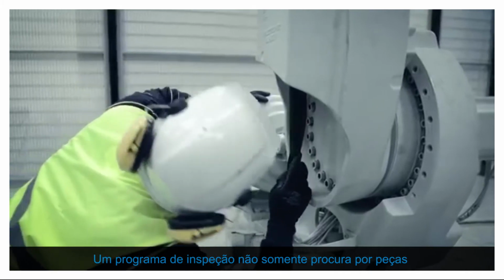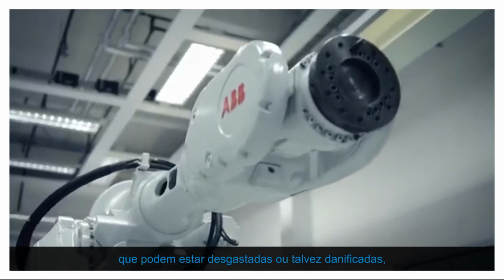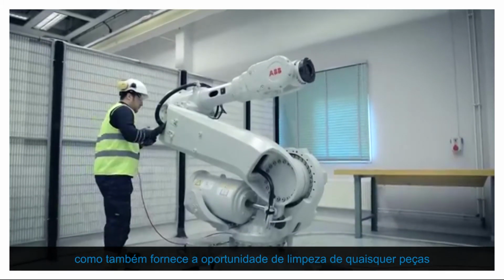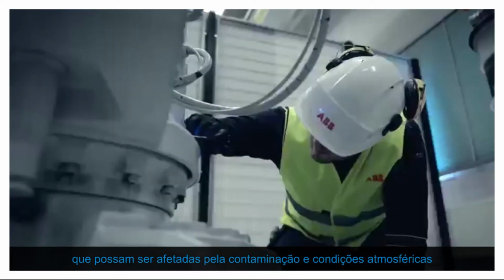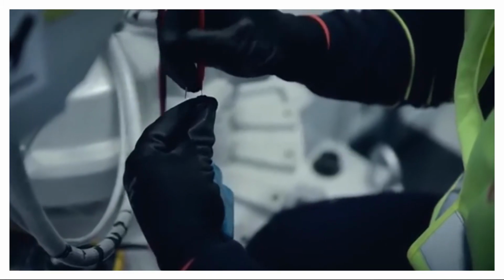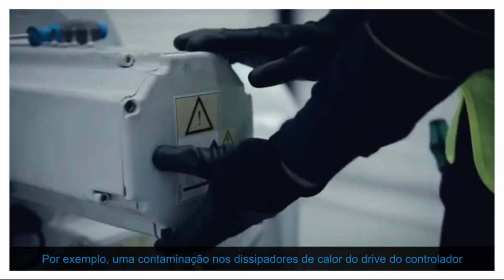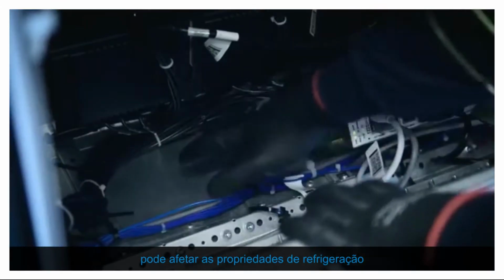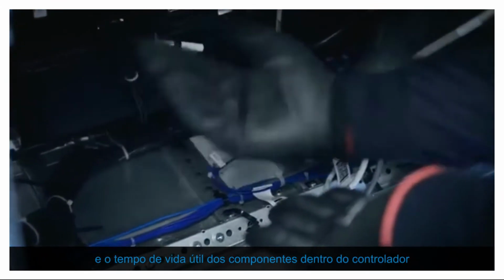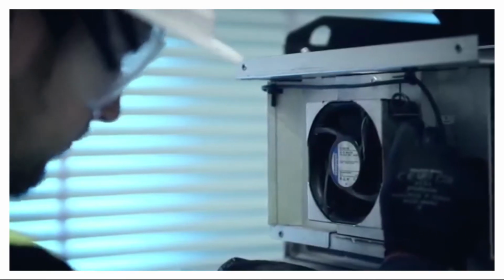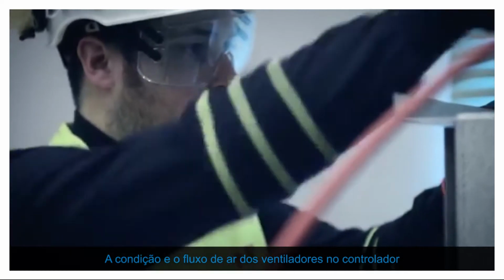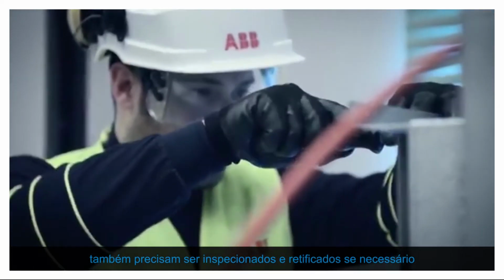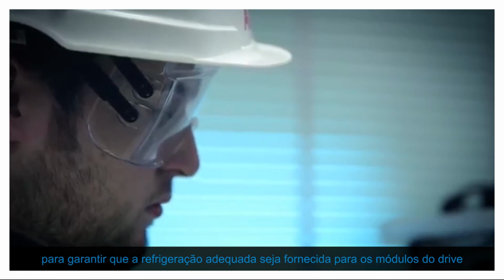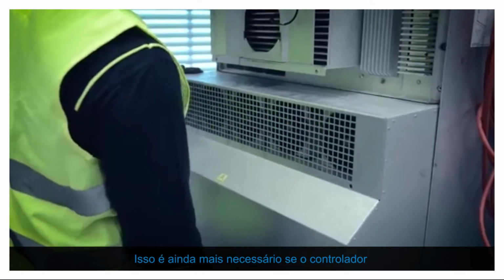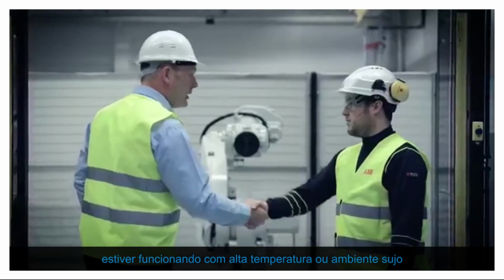An inspection program not only looks for parts that can be worn or perhaps damaged, but also provides the opportunity to clean any parts that may be affected by contamination and atmospheric conditions. For example, such things as contamination on the drive heat sinks of the controller can affect the cooling properties and thus the lifetime of the components within the controller. The condition and airflow of the fans on the controller also needs to be inspected and rectified if required to ensure adequate cooling is provided to drive modules. Particularly more so if the controller is working in a high temperature or dirty environment.